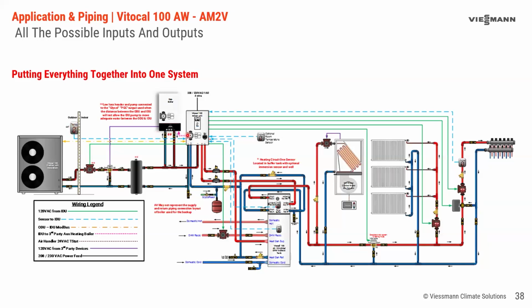And then we show again the connection between the boiler, the backup boiler and the heat pump indoor unit, and this one other line we haven't talked about at all. This other line here is the communication bus. So the outdoor unit gets all of its commands, the set point and whether it needs to be in heating or cooling, from the indoor unit.